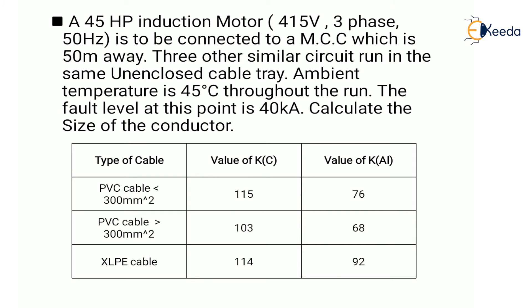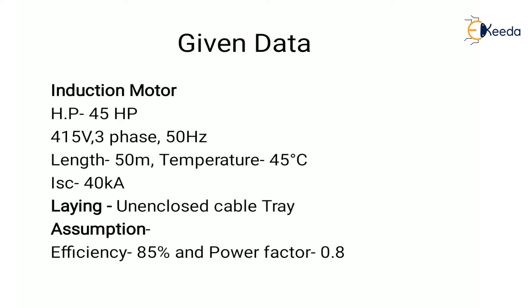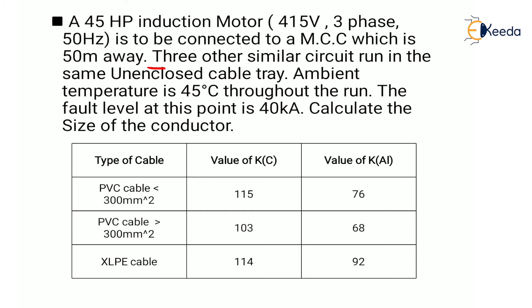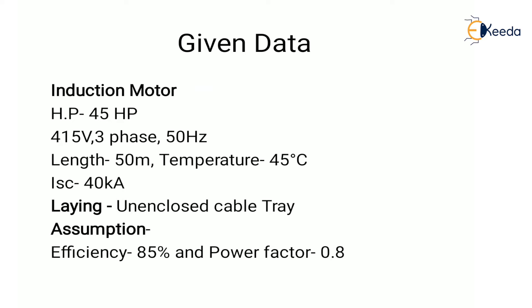Let's start with the solution. The given data: induction motor is 45 HP, 415V 3-phase 50Hz, length is 50 meters, temperature is 45°C, and short circuit current is 40 kA. The laying is unenclosed cable tray, as three other similar circuits run in the same unenclosed cable tray. We are assuming efficiency as 85% and power factor as 0.8.